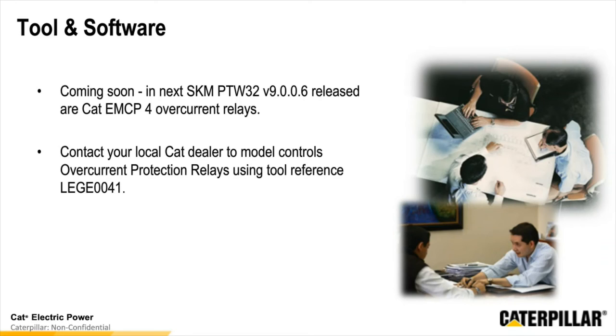Overall, there also is an overcurrent protection relay tool that Caterpillar has. You can work with your Cat dealer to model these different set points and make the decisions on whether or not you want to go with the normal inverse or maybe the thermal damage curve. It does include our thermal damage curve as part of it. So you'll be able to look at what you'll see with your product and what you'll be able to get with your Cat genset.